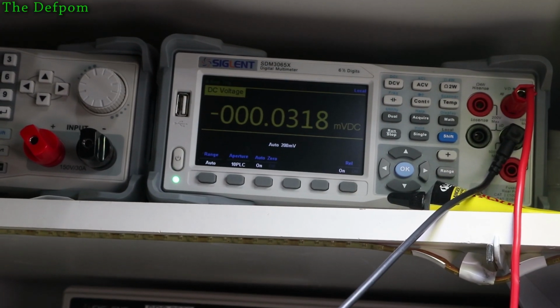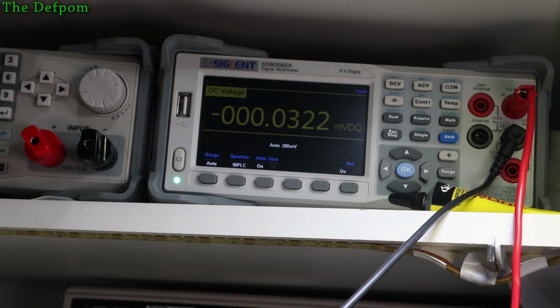So that's the reading we're getting at that test point. This is actually for the factory selected value of the resistor. If this is off, you have to change resistors on the board to match the factory selected requirements. If it's less than 50, you have to do one particular type, and if above, another. Anyway, I don't have to go there, thankfully. It's good. At least I know that board is definitely okay now. I probably need to redo the calibration of the ohms board, but that's not a big deal. I've got the calibrator. But it still doesn't explain why I was getting an error though.